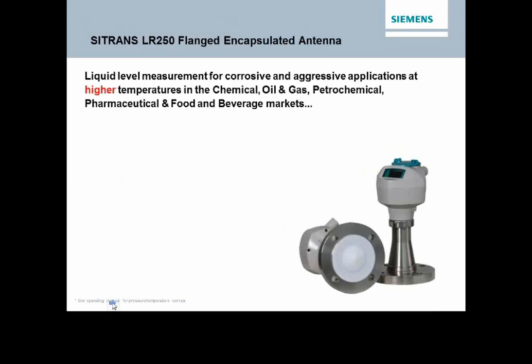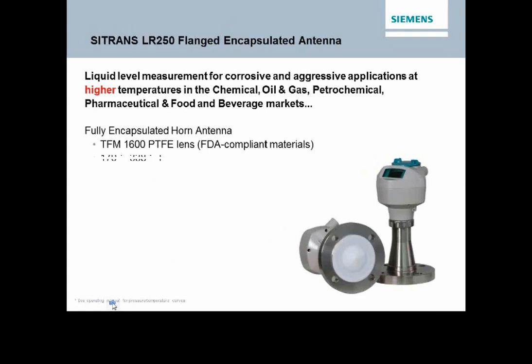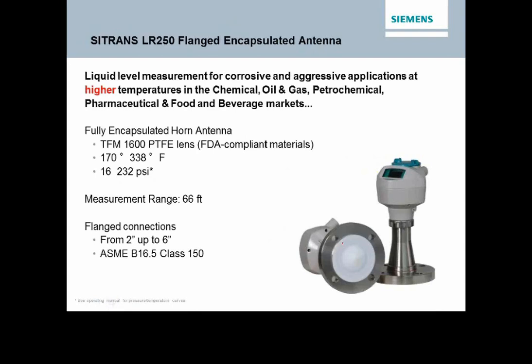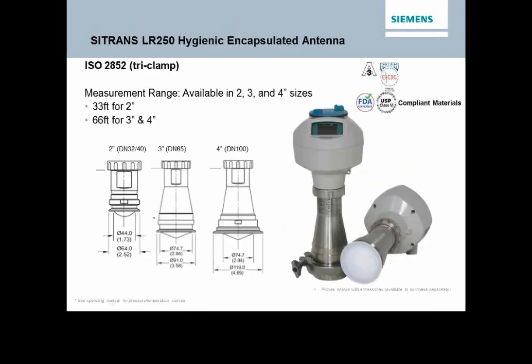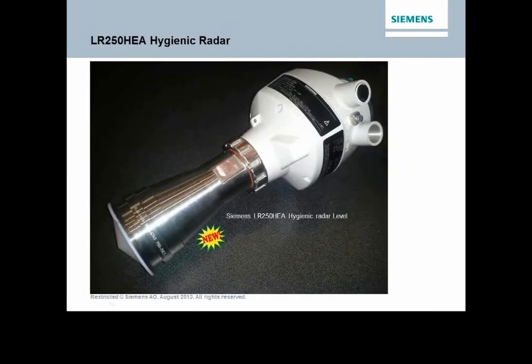So again, the flange encapsulated antenna allows us to do both corrosive and aggressive applications at higher temperatures in a number of industries. Since it's fully encapsulated, the process only sees the face here. Okay, so this would be a flanged application. We take a look at the tri-clamp style here. Again, the 2-inch size, 3-inch and 4-inch. Here's a close-up. As you can see, the process connection, this happens to be a 2-inch tri-clamp style. The process only sees the lens, okay?